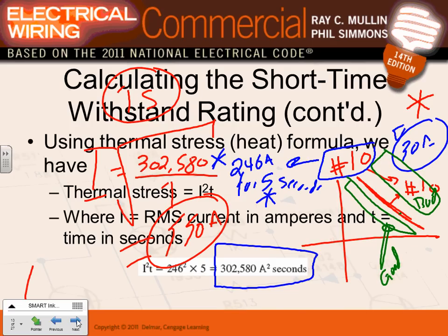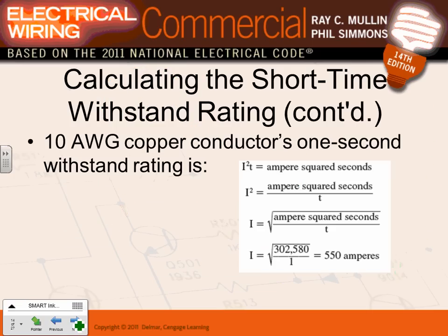If you hit the damage curve, it means the insulation has melted. Can you use it again if the insulation is melted? Not legally. You can, I guess, but not legally. When it's at the damage curve, the insulation has melted, and even the copper has evaporated. If you continue, you could get a short circuit. First, the insulation will melt. Second, the copper will evaporate. It will burn, like arcing. But hopefully, the circuit breaker will trip before you get into this value.